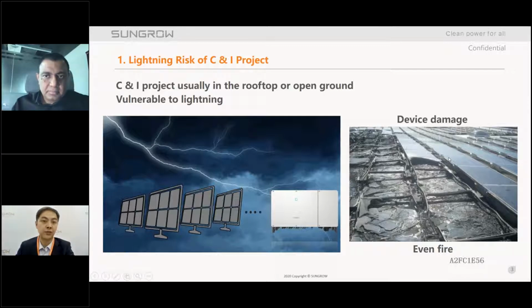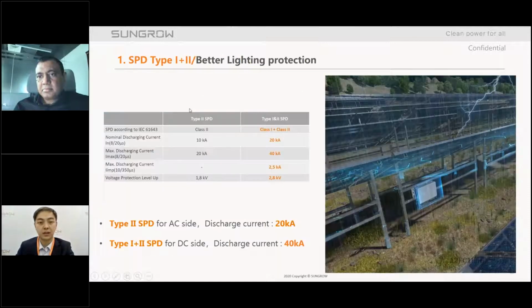As you can see from this table, the type 1+2 SPD ability is nearly twice that of type 2 SPD. Most importantly, type 1+2 SPD has the ability to resist even direct lightning. You see in this parameter, the inverter can resist direct lightning strikes of up to 2.5 kiloamps. This is the update for SPD protection, mainly for lightning on the DC side.